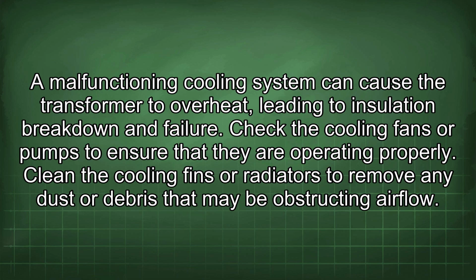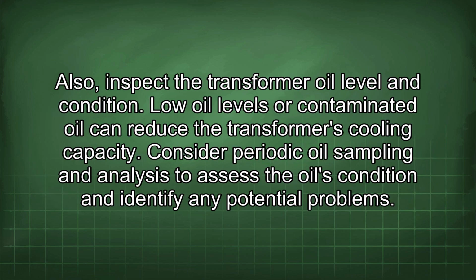Check the cooling fans or pumps to ensure that they are operating properly. Clean the cooling fins or radiators to remove any dust or debris that may be obstructing airflow. Also, inspect the transformer oil level and condition. Low oil levels or contaminated oil can reduce the transformer's cooling capacity. Consider periodic oil sampling and analysis to assess the oil's condition and identify any potential problems.